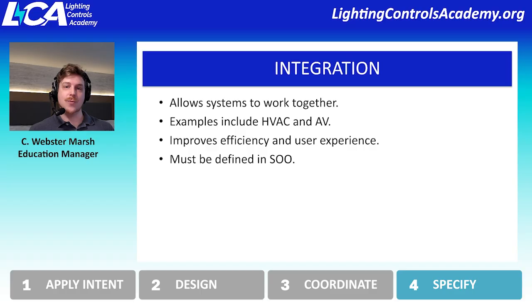But if you really want integration to be successful, you want to define it in the sequence of operations and clarify not only that there's integration, but what is that integration? What protocol is it using? What are the expectations of that integration? What happens when this trigger activates? Which systems are responding? How is it responding? There's a lot of information that needs to be outlined within integration.